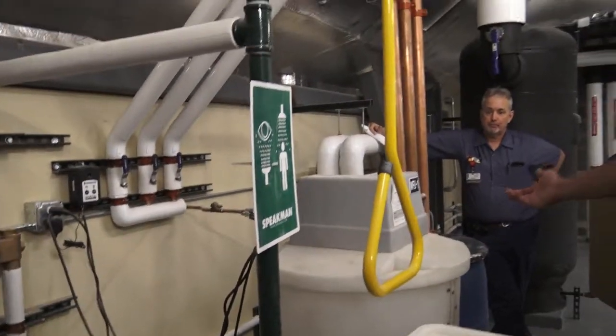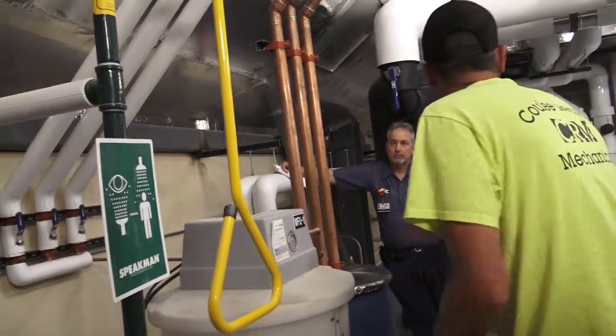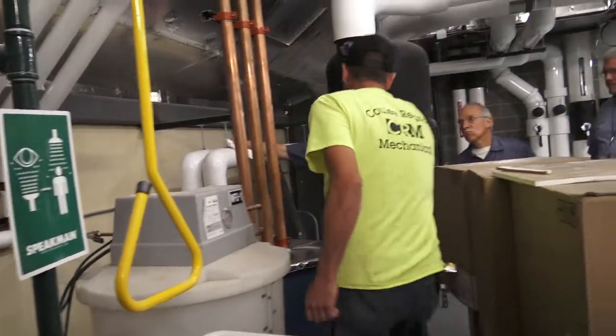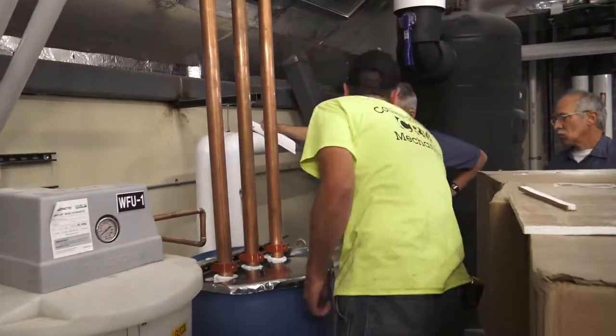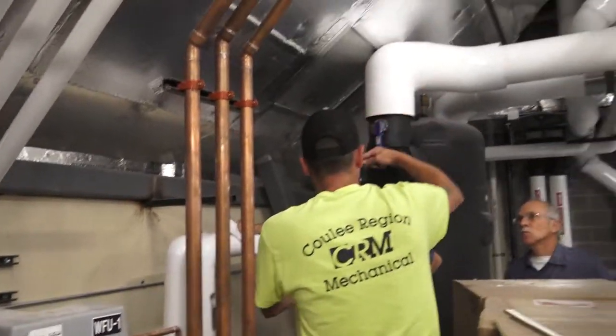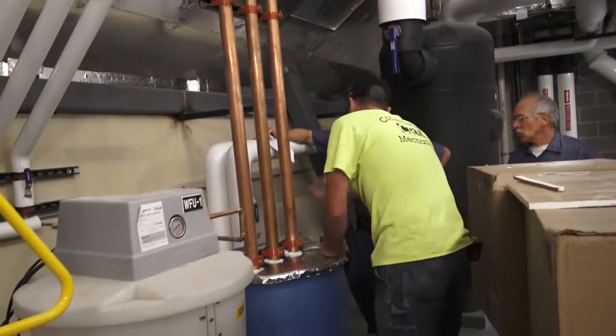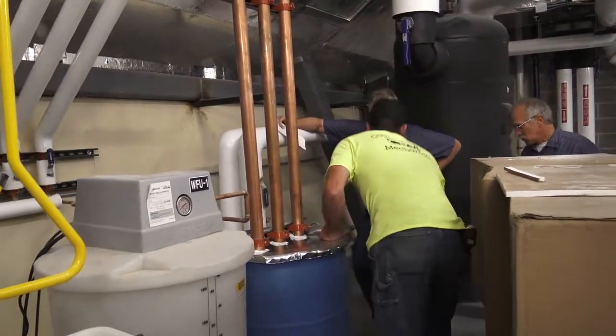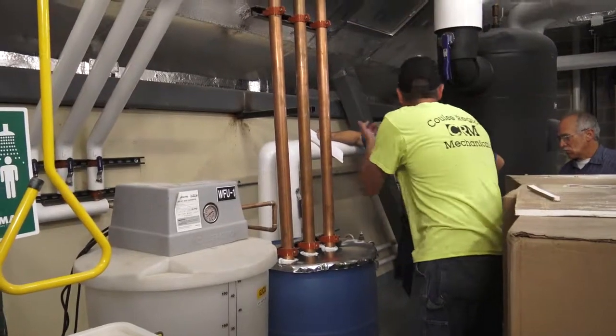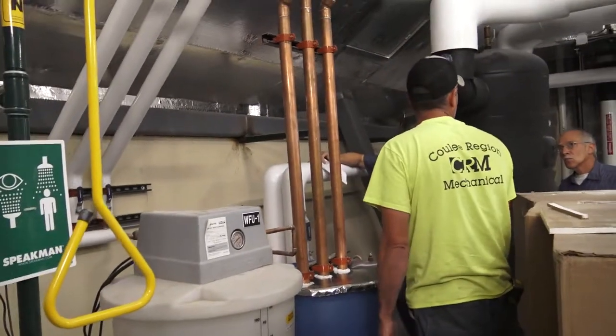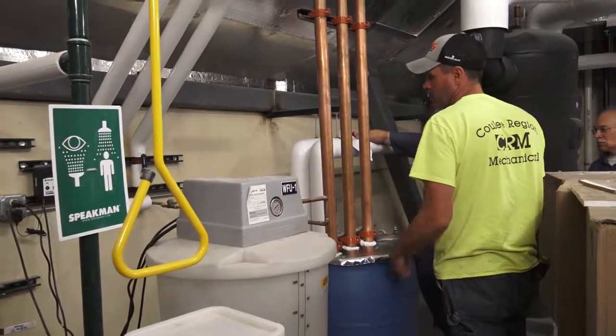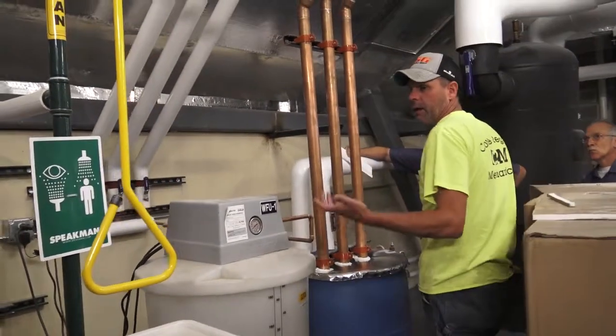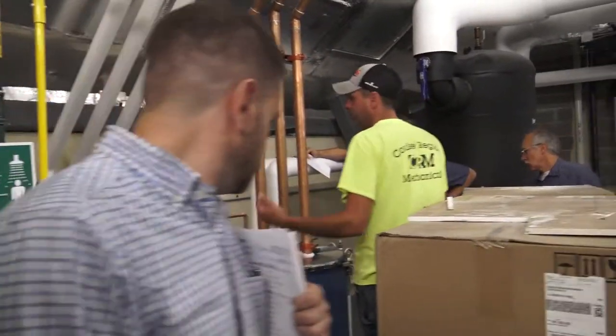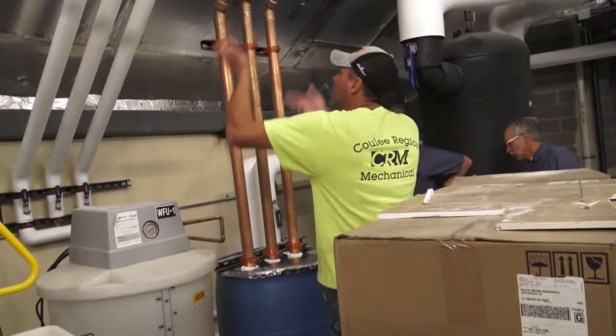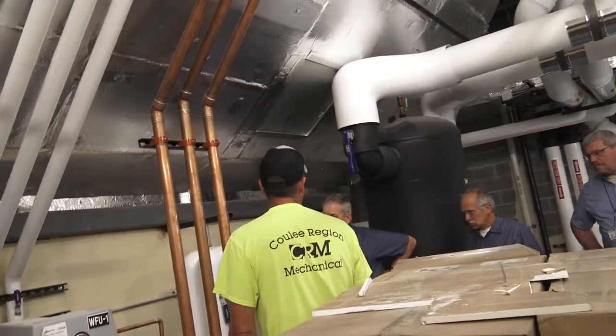And that's your relief valves, that'll blow down into there if you ever have any problems. And this is your strainer, that's what those long filters were, but they're short ones in there. So all you've got to do is shut that down, bleed it down, pull the basket out, pull whatever out. I'd say check that every 2 months too, see what's the matter with it. But yeah, everything's pretty much automatic, it does it by itself.